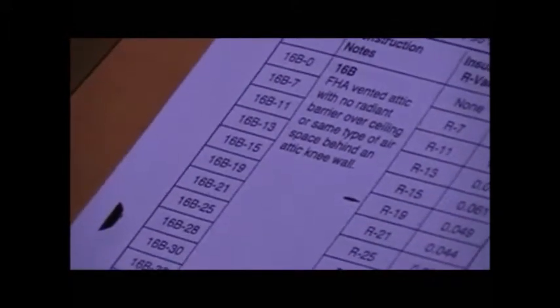I've gotta go, y'all remember, I almost done something wrong there. I've gotta go to the tab that says ceilings. So let me do that. There it is, ceilings. Okay, you can see that it says table 4A, construction number 16, 17, and 18. And we are using 16B-19 as our reference. Our U value for that was 0.049. So let's put in 0.049.